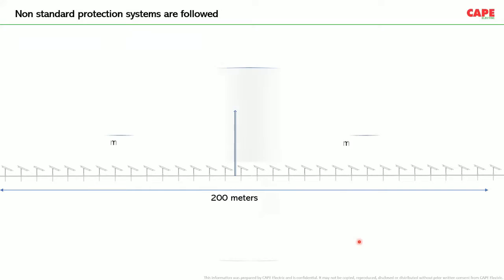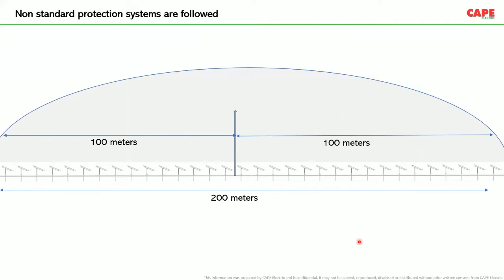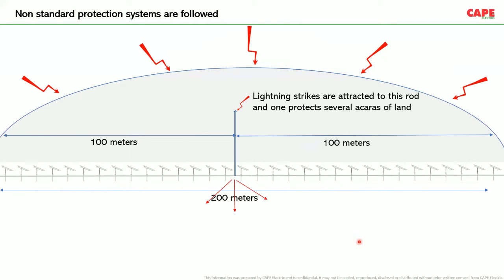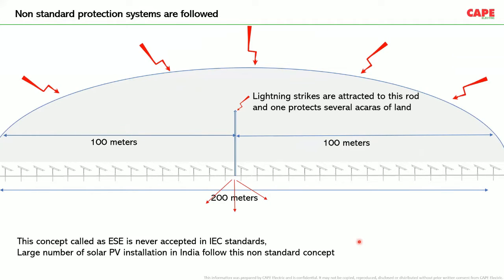Another issue which we see, especially in all solar systems, is lightning protection. Early streamer emission devices are used. The claim is that one device protects up to 100 meters. Please note that this claim is never accepted in the Indian standard or in the IEC standard. So these ESE rods are just for namesake. It won't protect your installation. If somebody asks, where is your lightning protection? You can show them, yes, I have a rod. That is my ESE rod. For namesake, you can keep it. Otherwise, don't expect any safety from these rods.